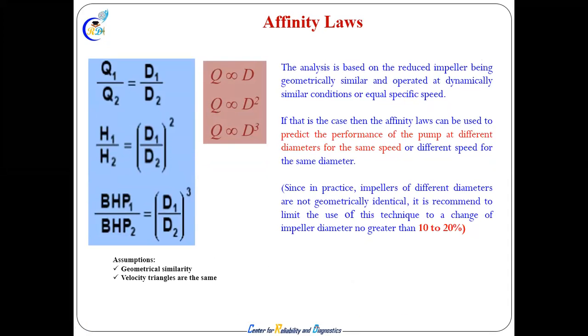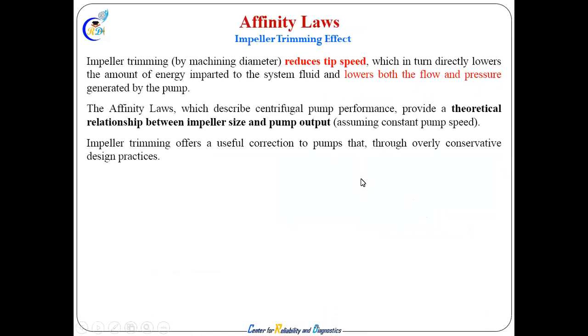And if you change the diameter of the pump, the impeller diameter, how does it affect power? Diameter change also affects horsepower similarly, so we cannot change it as we feel like. With a little diameter change, power changes a lot, by a factor of 8. If you increase the diameter, power is more; if you decrease the diameter, your power will be less. That is how it is done. Impeller trimming is very rampant in industry, and people are doing it very easily.